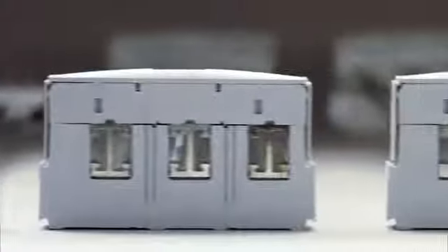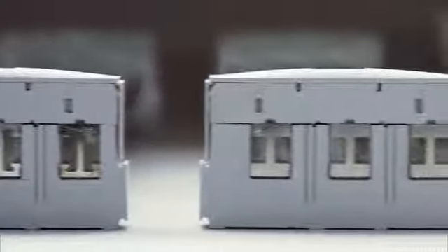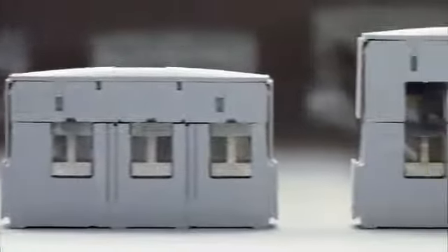The capacity of bus bar systems is increasing all the time, and they can be optimally adapted to the respective scope of application. They are based on commercially available flat bus bars in different cross-sections up to a maximum of 30 by 10 millimeters. These are supplemented by Woehner special profiles, such as the Double T, Triple T, and TCC profile for high power requirements. This enables currents of up to 2,500 amperes to be carried safely.